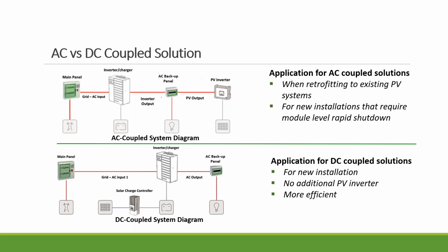Now, with the AC coupled, as you can see, you have two conversions. You have DC to AC, then you have AC to DC, right? So that certainly has some efficiency loss, somewhere between 5 to 10%, depending on the manufacturer and depending on the technology as well. And a DC coupled solution is that you do not have a PV inverter.